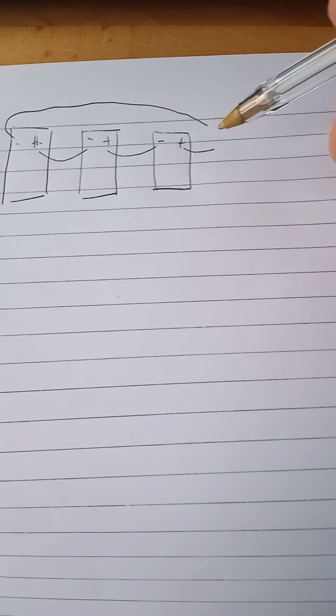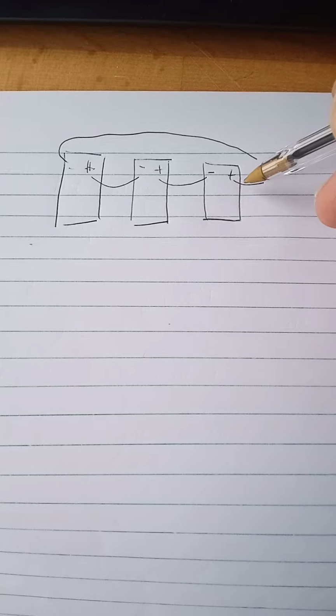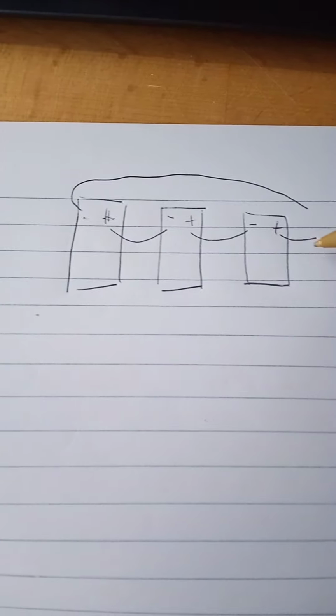Remember, I'm just doodling these drawings here. These cables, the positive line and the negative line as well, they both need to be the same length in order to ensure that you've got no uneven balance in the system. And that's the same for the cables going from the controller to the batteries and from the batteries on to the equipment that they're running. So try and make sure that your cable lengths are the same, even if in reality they don't need to be. So you may have, for example, at one end of your panels, your controller. Well, you're going to need to create your positive line, in this case, the same length as this one, and then just curl the wire up, taking care, obviously, that you don't create pockets of heat in the system. So that's an example of series wiring.